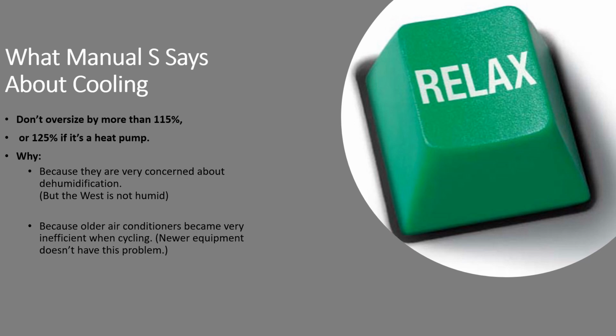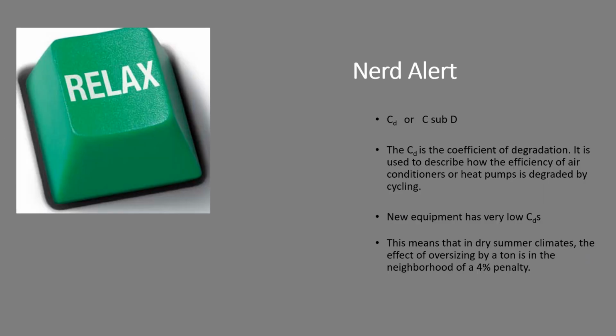But Manual S says about cooling: don't oversize by more than 115% or 125% if it's a heat pump. We don't have to worry about that oversizing of air conditioner too much. Of course you can oversize air conditioners, but the reason they're so worried about that is dehumidification. And when we are at 95 degrees, chances are that air conditioner is running a long time. It's not very humid outside, and as that air conditioner runs, it even dries the indoor air out more and more.